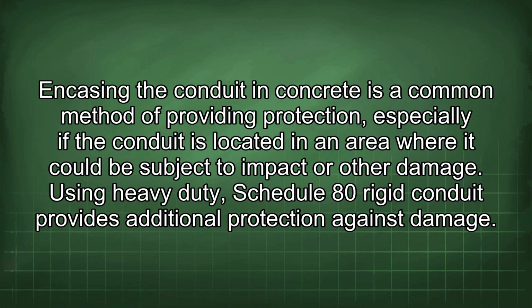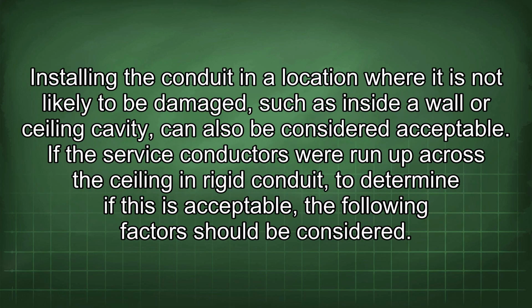Encasing the conduit in concrete is a common method of providing protection, especially if the conduit is located in an area where it could be subject to impact or other damage. Using heavy-duty, Schedule 80 rigid conduit provides additional protection against damage. Installing the conduit in a location where it is not likely to be damaged, such as inside a wall or ceiling cavity, can also be considered acceptable.